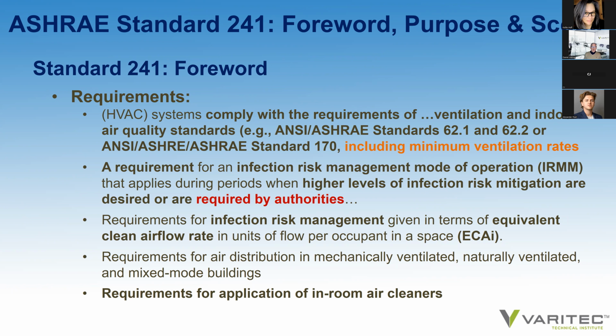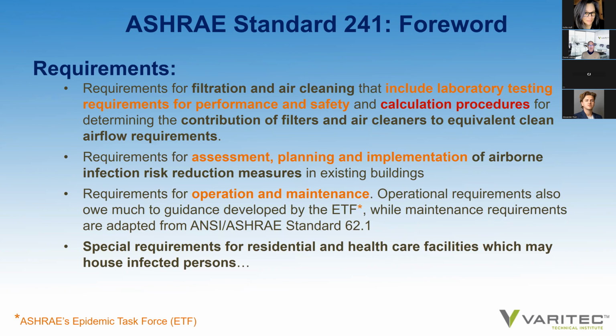There will be a requirement for an application of in-room air cleaners, and it provides a standard for those cleaners that was previously lacking. There is a requirement for filtration and air cleaning that these technologies include laboratory testing for safety and performance, and provide calculation procedures for determining the contribution of filters and air cleaners to achieve equivalent clean airflow requirements. There is a requirement for assessing, planning, and implementation of the standard to go into infection risk management mode. And it offers guidelines on operation and maintenance of these systems for building owners.